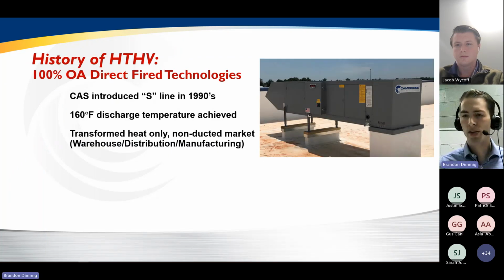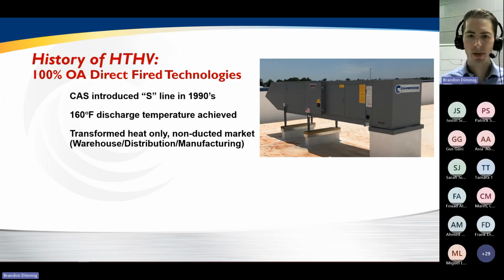A little bit on the history of HTHV. Back in the 1990s, we introduced a product line under the S-Series nomenclature, and we achieved some really cool results in that we were able to hit 160-degree discharge temperature with a proprietary burner system. And this product line was transformational to the heat only, non-ducted market, particularly in warehouses and distribution and manufacturing. It's of course expanded since then, but it was a really unique value proposition then, and it still is now.